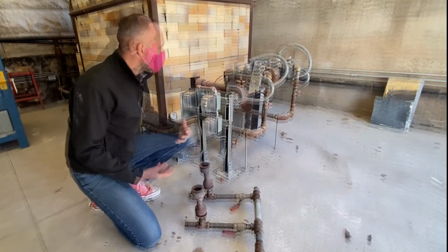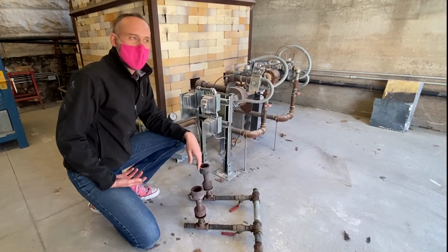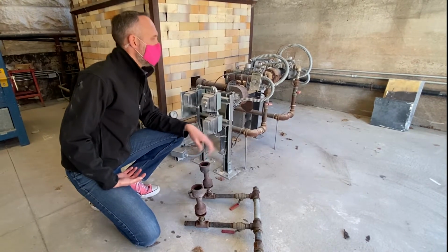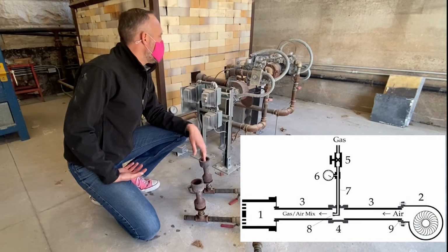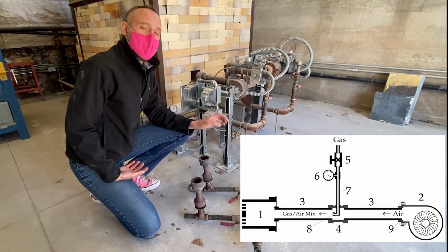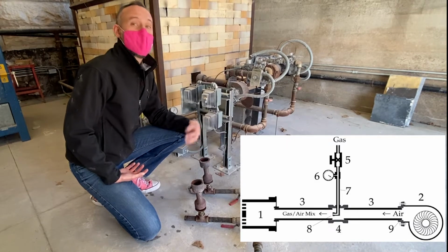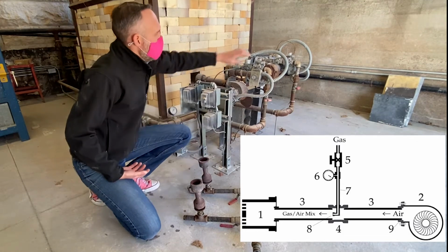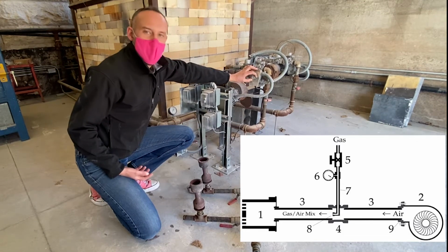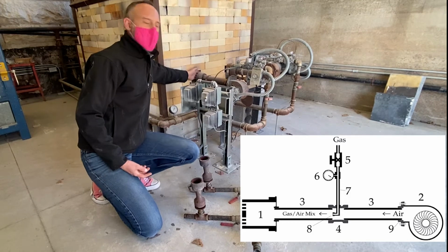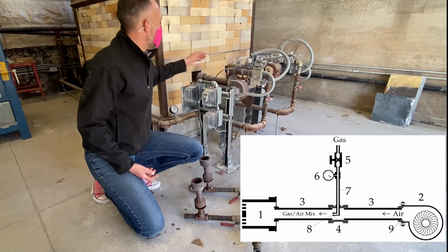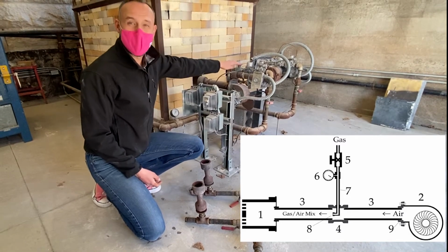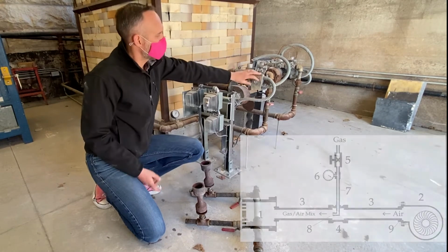The biggest distinction is that a forced air burner, like the name sounds, has a forced air system. This allows us to use electricity to introduce air, essentially more oxygen, which allows us to put more fuel through the same system so that we get more heat. You can see that clearly here. If we turn this on, you can hear that squirrel cage fan blasting away. Then to meet that system, we could put in a lot more gas to get more temperature.